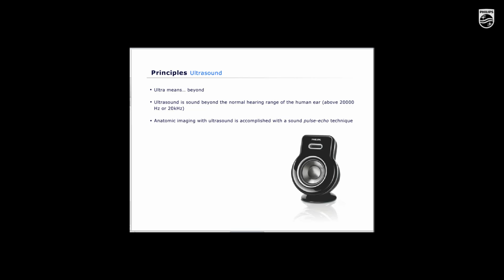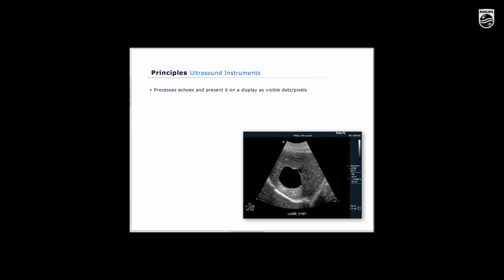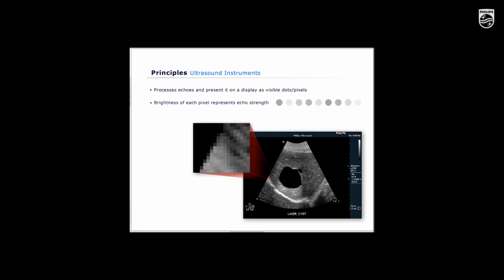Medical ultrasound is a non-invasive way to look inside the human body using ultrasound signals. Ultrasound instruments transmit ultrasound pulses and then receive the echoes of the same pulses. Based on the time between the transmit and the receive, the ultrasound system will place a dot or pixel onto the screen. The brightness of each pixel represents the echo strength, and the location of the echo represents the location of the echo structure generating the return echo.